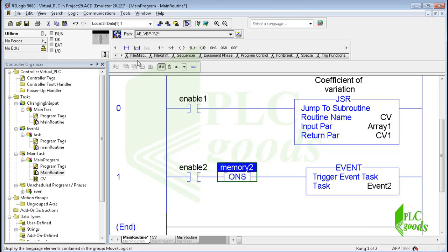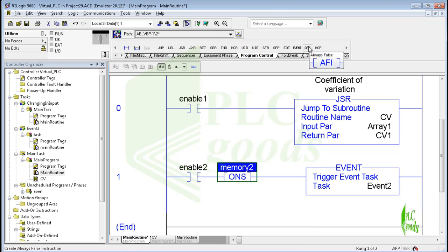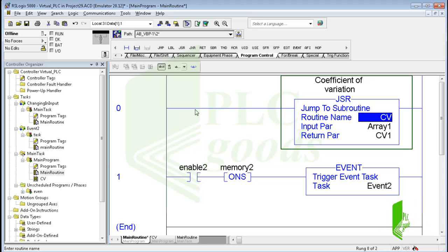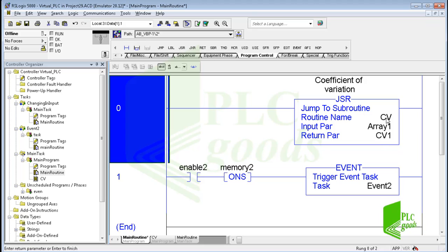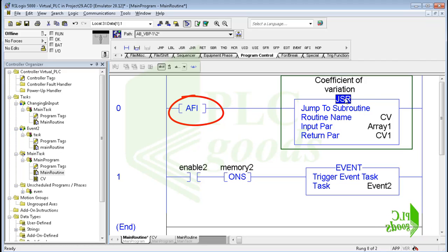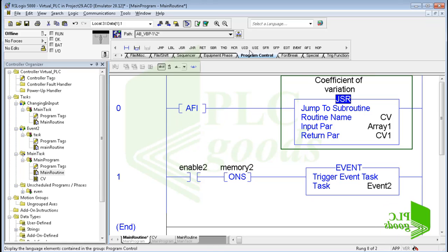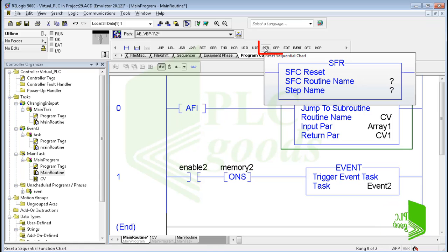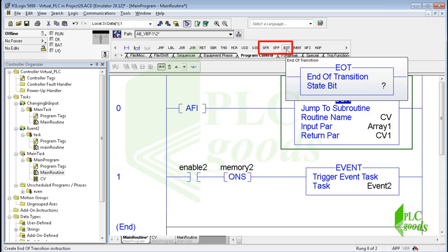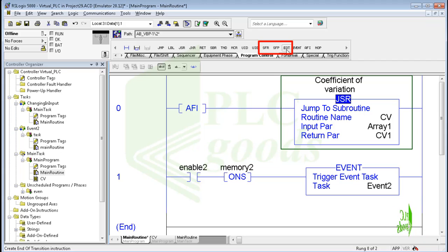The next instruction of the program control group is AFI — always false instruction. This instruction is executed based on the contact state. If I remove the contact, the controller will execute the JSR instruction always. But if an AFI instruction is placed at the beginning of the rung, the controller won't execute the JSR instruction. All instructions of the program control group have been explained except the sequential programming instructions, which I will cover in the next video to do an automatic warehousing project with Factory IO software.